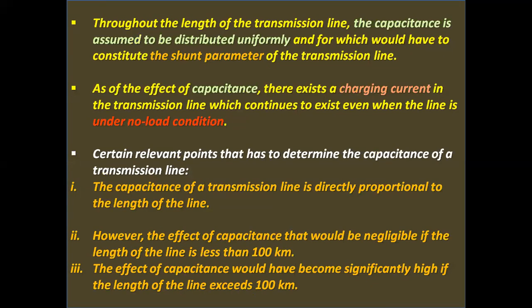Throughout the length of the transmission line, the capacitance is assumed to be distributed uniformly, and this constitutes the shunt parameter of the transmission line. As an effect of capacitance, there exists a charging current in the transmission line which continues to exist even when the line is under no load condition or lightly loaded condition.